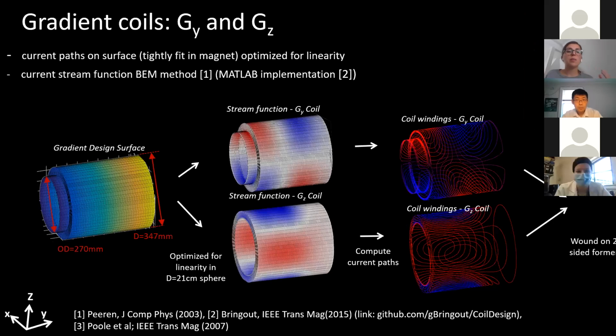Okay, so we use that built-in permanent magnet for one of the encoding directions, the X direction. But to encode in the other 2 dimensions to create 3D images, we use coils to create gradient fields, called gradient coils, in the Y and the Z directions. So we designed 2 efficient gradient coils to create the image encoding fields in those directions.